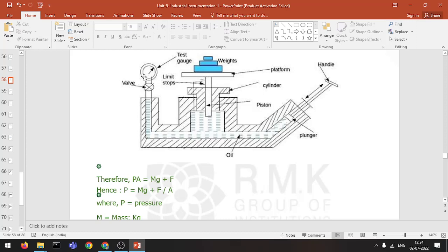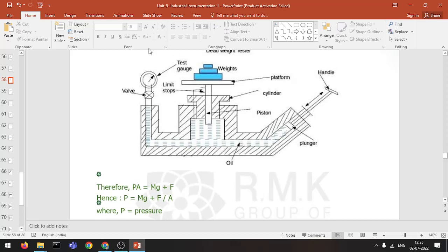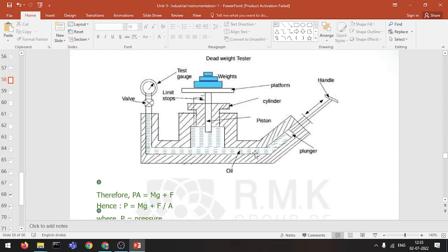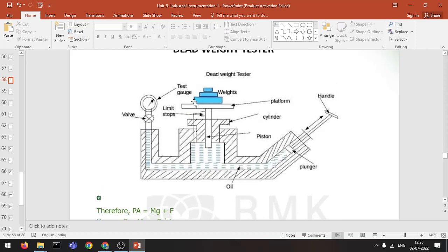The pressure value shown by the gauge should be equal to the known input pressure P, whichever we have calculated. If the gauge indicates some other value, then the gauge has to be adjusted so that it reads the value which we have measured earlier. This is how calibration of a pressure gauge is done. I believe that you are able to understand the working of a dead weight tester.